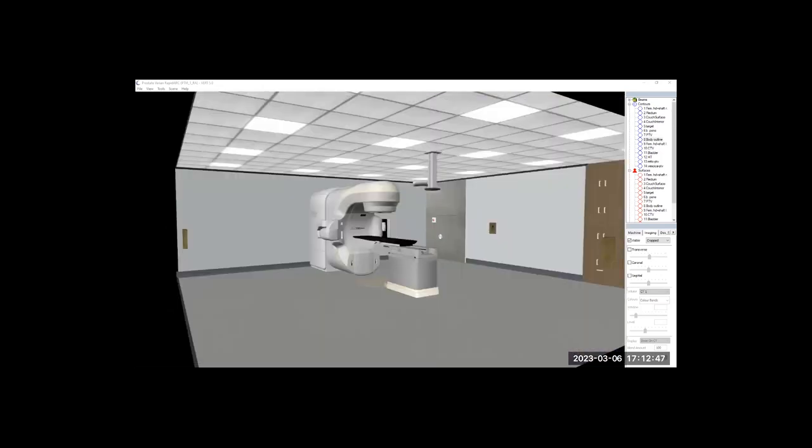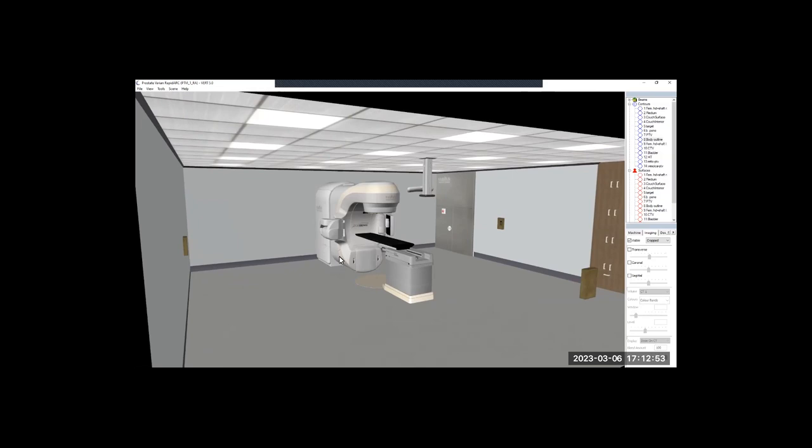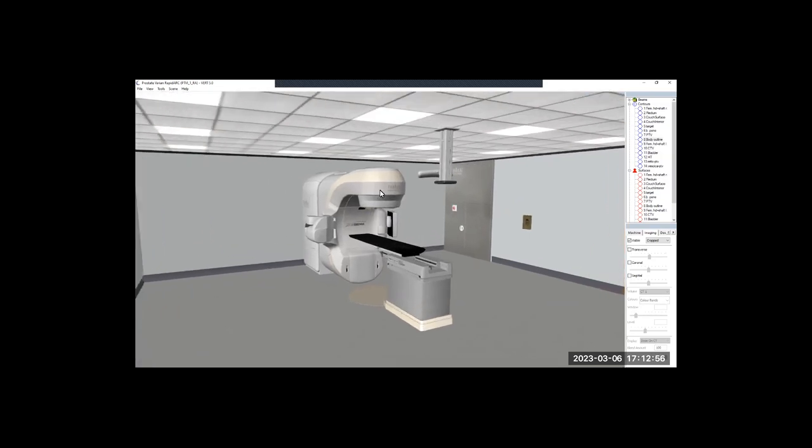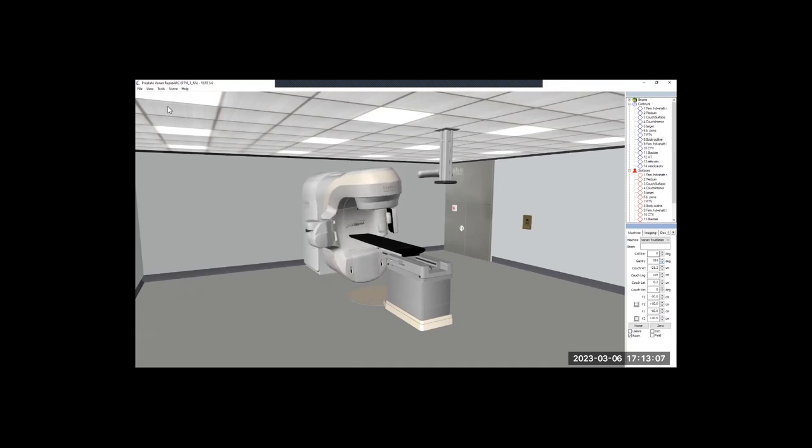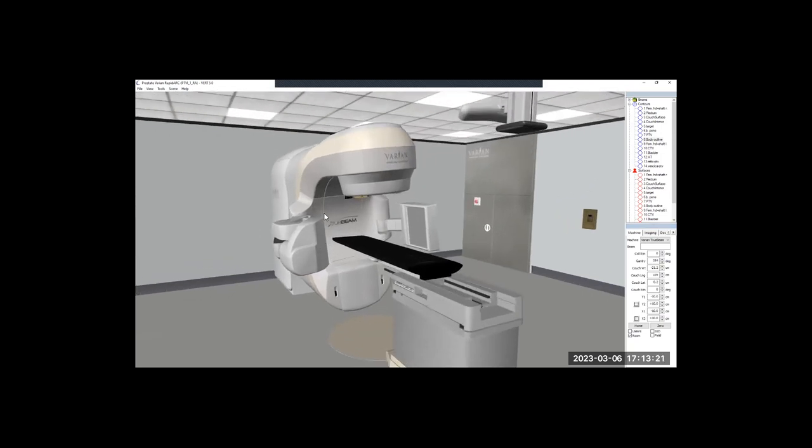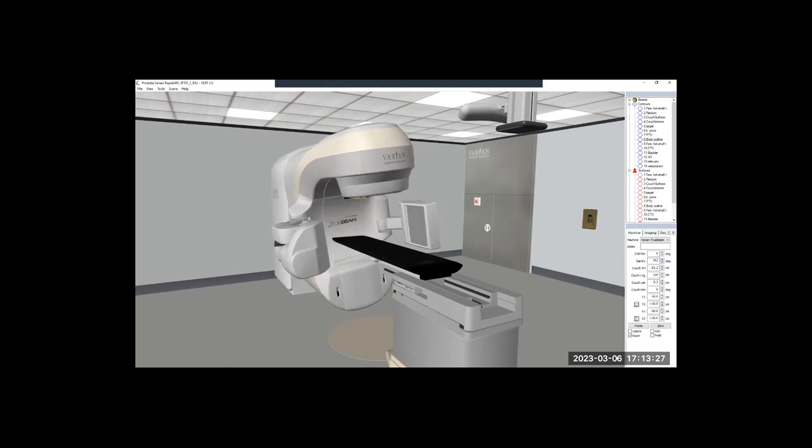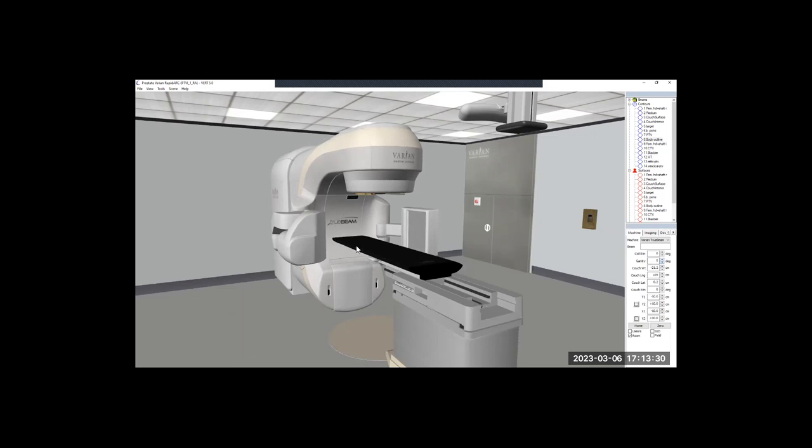So an overview. Here is a radiotherapy bunker. It has radiation shielding around the outside. This is our linear accelerator. This machine generates those high energy x-ray photons, as I mentioned earlier. This machine has the handy tool that it can rotate 360 degrees. It can take medical images using onboard imaging, which is excellent. We've got an x-ray and we've got the detector out here, an x-ray tube and the detector so they can take patient images whilst they're actually on the bed and even rotational images too. This is absolutely critical before they start the radiation beam on to make sure the patient's in the right position.